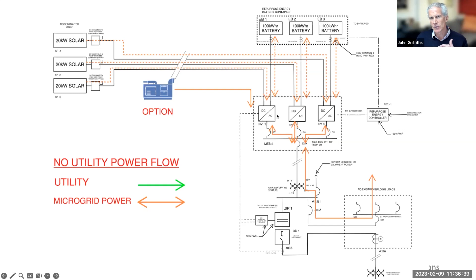I think one takeaway many of you may already notice is that if you connect a generator through a hybrid inverter to a system—we're actually doing that at one project—normally a generator connected to a building is sized on the biggest load in the building, typically an elevator or a chiller, because it needs that capacity to start and run that motor. What does that mean?